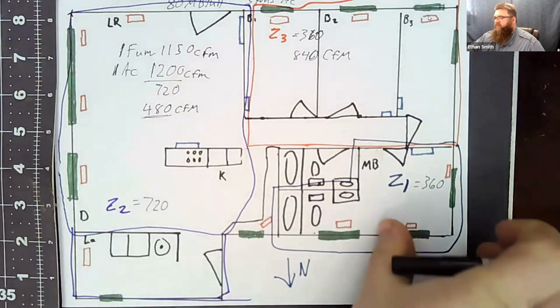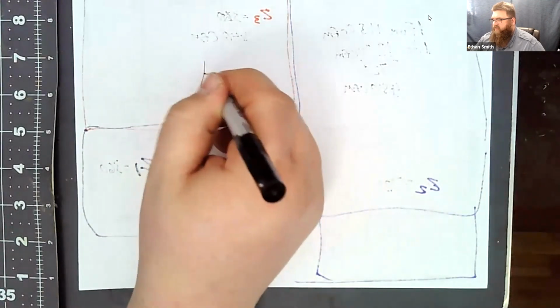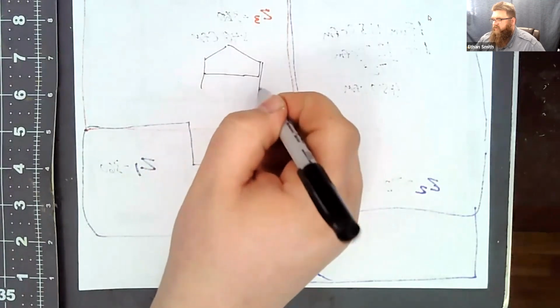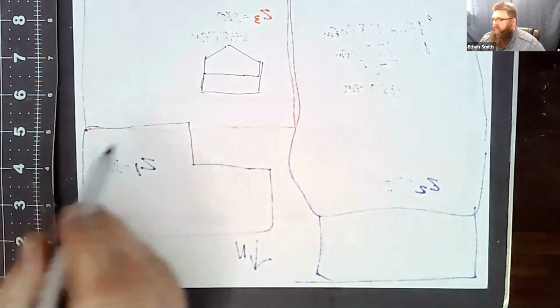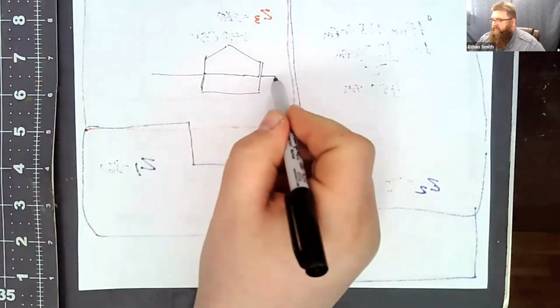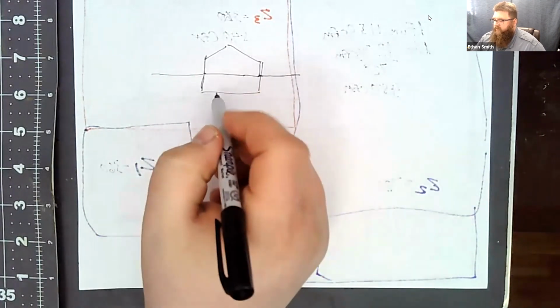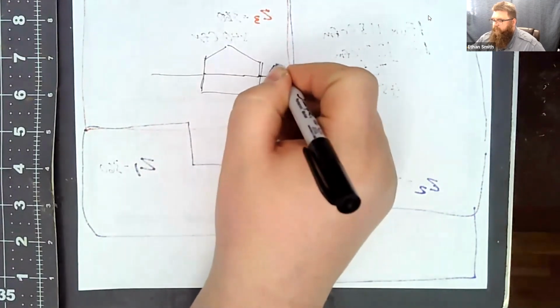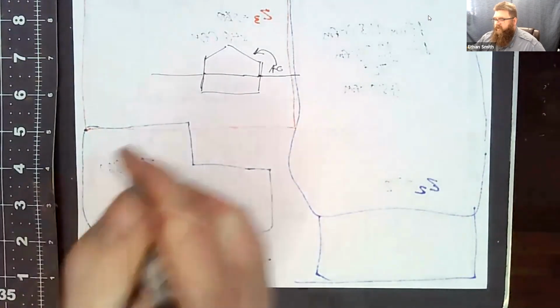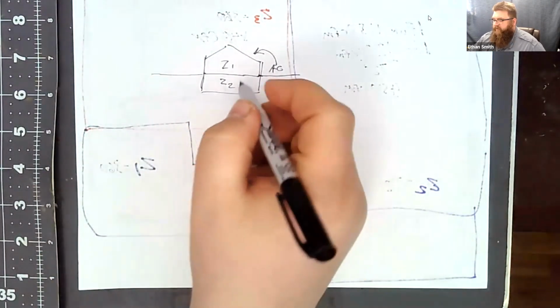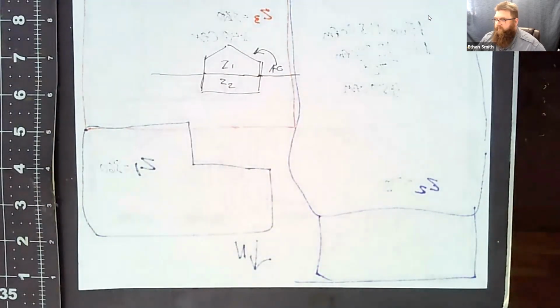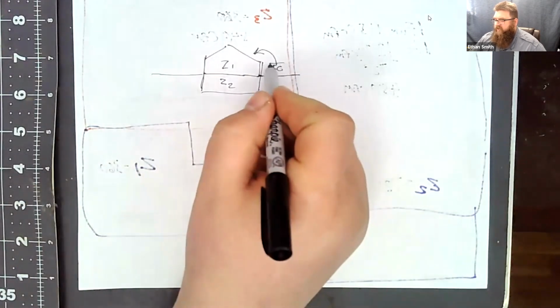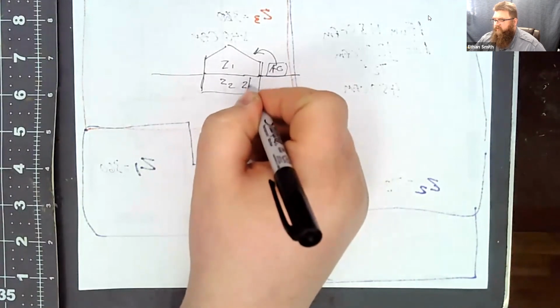Okay. I'll tell you guys where single stage equipment zoning works most of the time. And that's when your house isn't all one level, it's when your house is 2 levels. They do this up in Idaho a lot. They do it in northern Utah a lot, where you've got a house that has a full below grade basement that needs heat in the winter, but never needs cooling in the summer. And so they size the AC for the upstairs load only. And then they can do zone 1, zone 2. Okay. And then they size the furnace to take care of the whole house. Okay. But usually in this case, even though you've only got a single stage AC, we're going to run a 2-stage furnace so that we can split our capacity up and down.